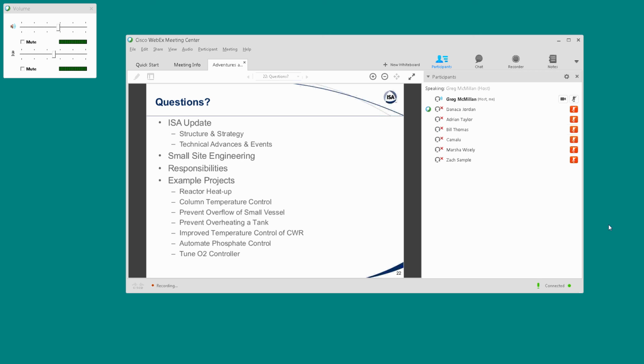So you need to make sure that your rate time is not more than about 1/4 of the reset time. People have literally taken their settings over from the old DCS system that had the series PID form, and put them into their new DCS systems with the ISA standard PID form, and really gotten into some very severe oscillations because the rate time was so large and was either approaching the reset time or larger than the reset time.